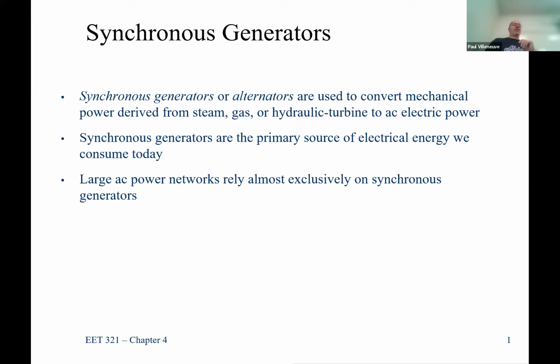That's not to say there aren't synchronous motors running fully no load, meaning they're just spinning and not doing any mechanical work. I worked on a project a few years ago in New Hampshire. PSNH likes to use these things called synchronous condensers, which is basically a synchronous motor without any load, and the purpose is to support the system under heavy load conditions or fault conditions typically.